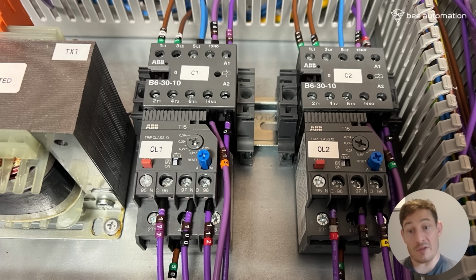If that trips out, if it overloads, depending on what we've got it set to here on this dial, that then opens, that goes open circuit, which cuts the power to this contactor, which in turn cuts the power on this other side, going off to those terminal blocks and off to the pump in the field. And then on the normally open contacts here, which are normally open in a healthy condition, when that does trip, they will then close, and that will be going off to our relay, which will energize, and then we can have various things happening off that relay. In this case, we've got it energizing a light on the front of the panel for a visual representation, and then also with a different voltage going into the PLC to let us know and send a push notification, an email, text message, or we can just program something off the back of that input telling us that this pump has tripped out.